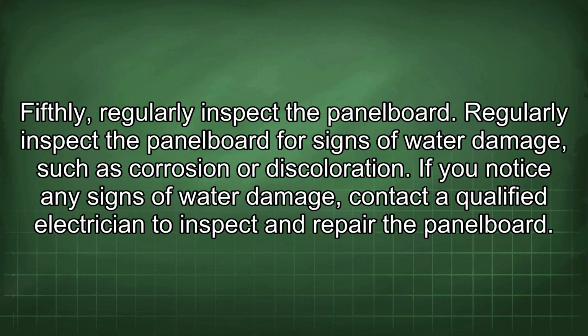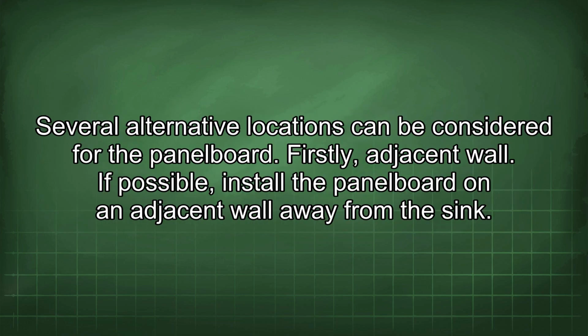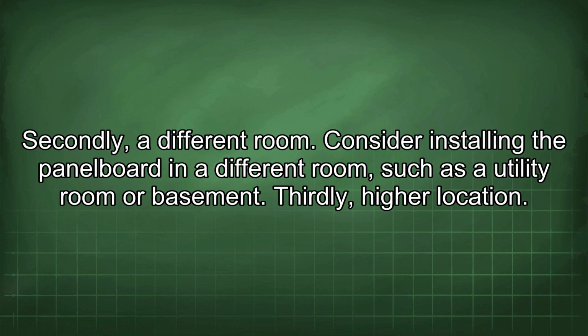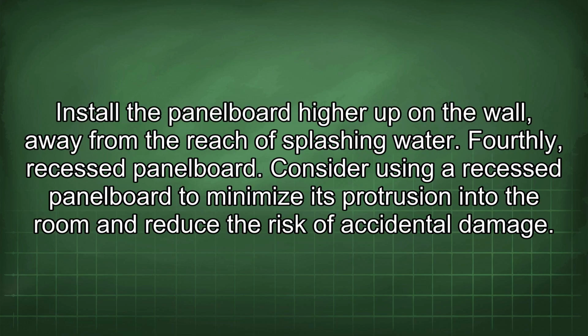Fifthly, regularly inspect the panel board for signs of water damage such as corrosion or discoloration. If you notice any signs of water damage, contact a qualified electrician to inspect and repair the panel board. Several alternative locations can be considered for the panel board. Firstly, adjacent wall. If possible, install the panel board on an adjacent wall away from the sink. Secondly, a different room. Consider installing the panel board in a different room, such as a utility room or basement. Thirdly, higher location. Install the panel board higher up on the wall, away from the reach of splashing water. Fourthly, recessed panel board. Consider using a recessed panel board to minimize its protrusion into the room and reduce the risk of accidental damage.